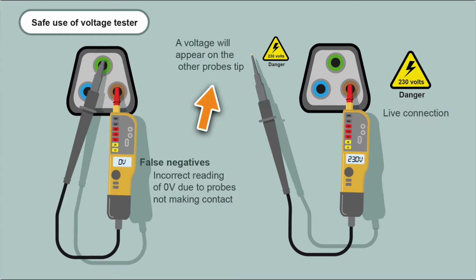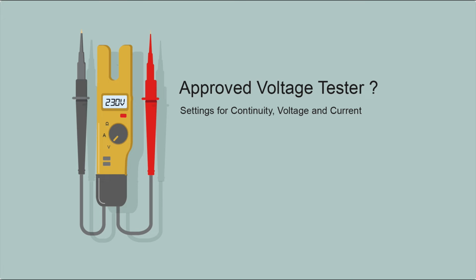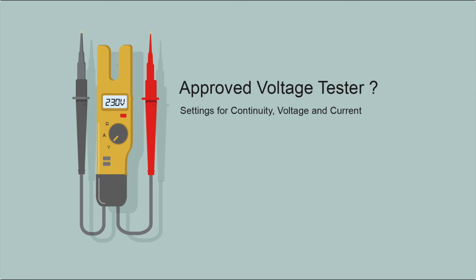And another thing to bear in mind as well, if you have got a live connection on one end of your voltage tester, a voltage may appear on the other probe. So good care needs to be taken there. And when you're buying a voltage tester, I think it's best to have one that purely just measures voltage. Some have a dial that you can turn to current and continuity. And the issue with them is that you might have it on the wrong setting. Again, I've got a little video on this.